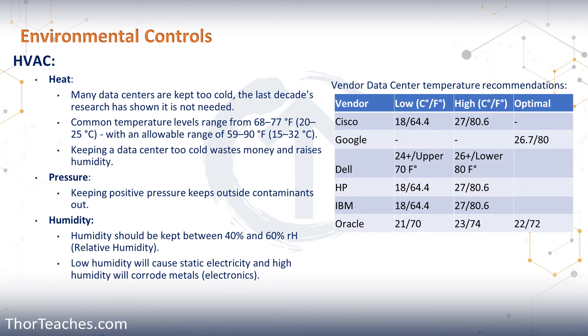It has for decades been really common to keep our data centers very, very cold, but keeping them that cold is really not needed. It doesn't necessarily have an adverse effect on the equipment, but it can waste hundreds of thousands of dollars every year to keep our data center 5 or 10 degrees lower than it actually needs to be. If you look at the image over here on the right, you can see some vendors' recommendations — these are the optimal ranges for their equipment to function, somewhere between 68 and 77 Fahrenheit, or 20 to 25 degrees Celsius.